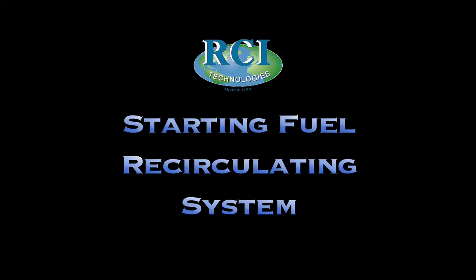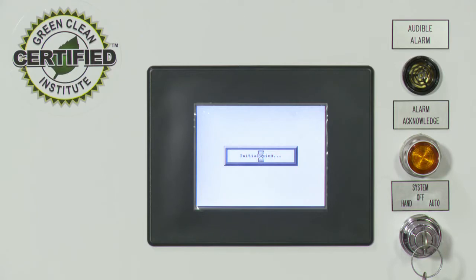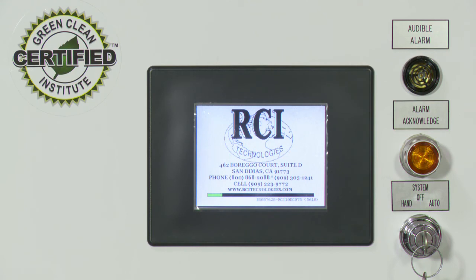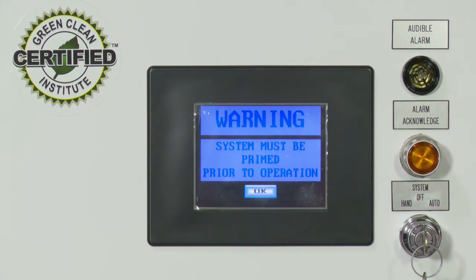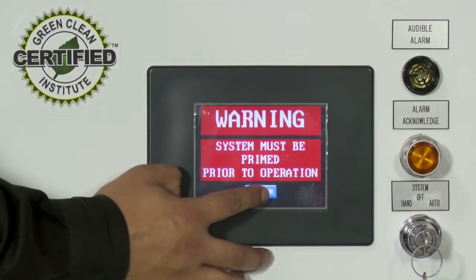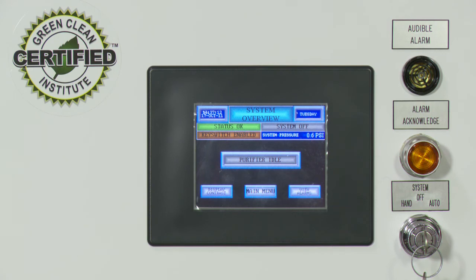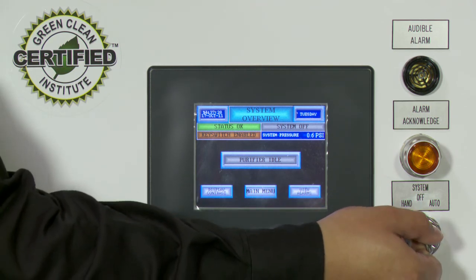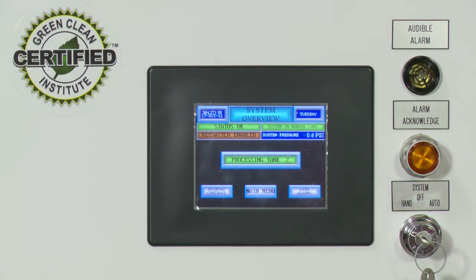And now, starting the fuel recirculating system. After you have primed your system, you are now ready to go through the initial startup. Upon initial system power-up, the RCI power-up screen will prompt. Next, the prime warning screen will prompt. Press OK, and the system is ready to run. The system will begin pumping once the system HOA switch, located on the exterior front of the enclosure, is switched to the hand or manual position.